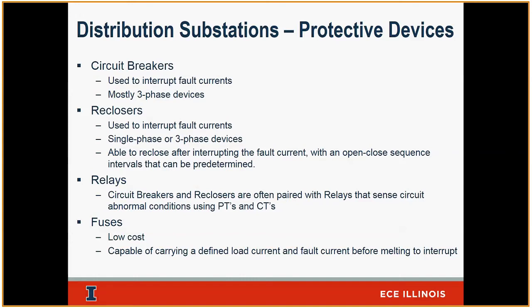The recloser will open right away because it will see a fault. The recloser can be programmed to wait a small amount of time and then try to close again, to see if that fault is still there or not. Did the tree come off? Are things back to normal? So instead of my customer seeing an outage, I'm going to risk it and open the device, and see if I can close it real quick. Our typical sequences on the distribution side are 5, 15, and 30. So I open, and then I wait 5 seconds. Then I come back hot and close and try the line, to see if it's going to stick, meaning it's going to stay hot. There's no fault. The fault is not there. I don't see it anymore, so we're good to go.